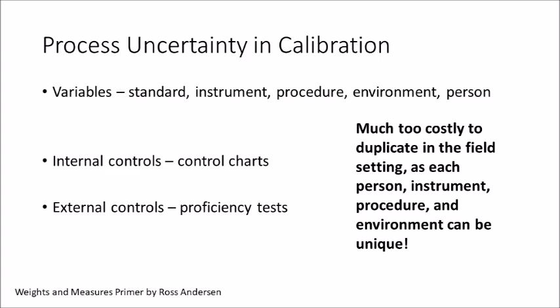The simple fact is that if we try to duplicate this in the field setting, with each person, instrument, procedure, and environment being unique, we would literally be making control charts for each instrument that we test. And the fact is, calibration verification is not what's done in the field. And how do we know that? Well, let's look at the compliance decision in Handbook 44.